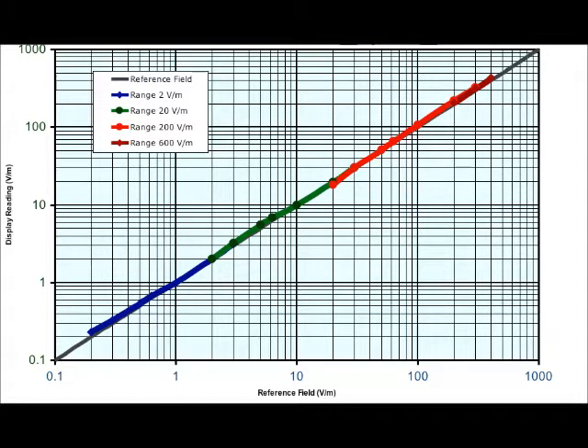Figure 1 shows a linearity plot of this meter and probe that we tested versus the reference field. You can see that the field is changing from 0.2 volts per meter to 400 volts per meter, and this is axis X, and on axis Y you can see the real reading of the meter. If you have an ideal instrument, you should get a straight line. Any deviation from a straight line means linearity error. In our case, the linearity error is on the order of plus minus 1 to 1.5 dB, depending on the field.